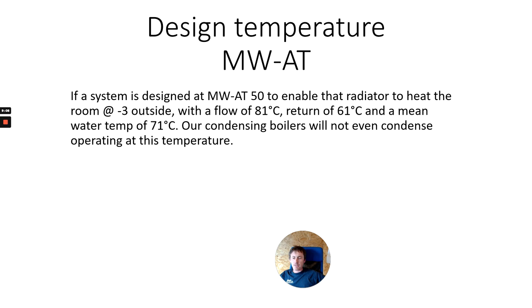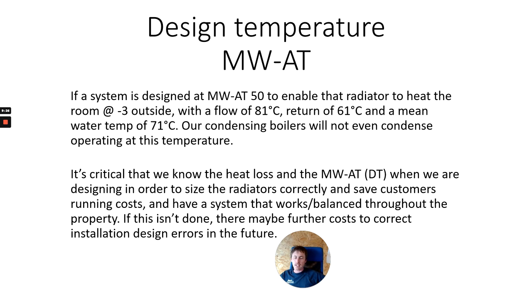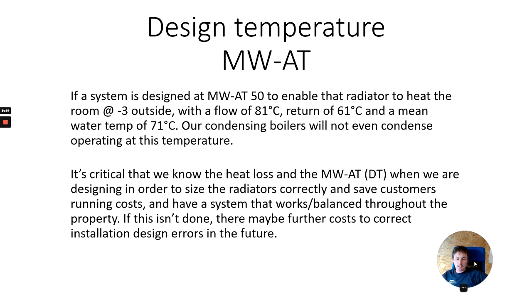If the system is designed at a mean water to air temperature of 50 to heat the room at minus 3 outside — with a flow of 81°C, a return of 61°C, and a mean water temperature of 71°C — our condensing boilers will not even condense operating at those temperatures. It's critical that we know the heat loss and the mean water to air temperature when designing, in order to size radiators correctly, save the customer running costs, and have a balanced system throughout the property. If this isn't done there may be further costs to correct installation design errors in the future — as basic as wanting to change a radiator can instantly create an imbalance.